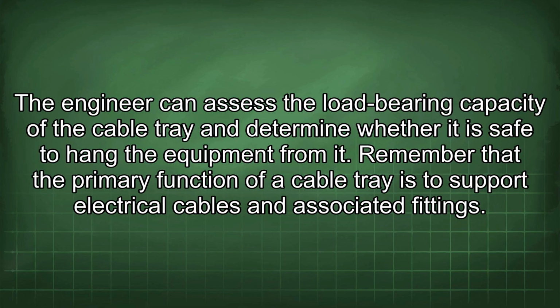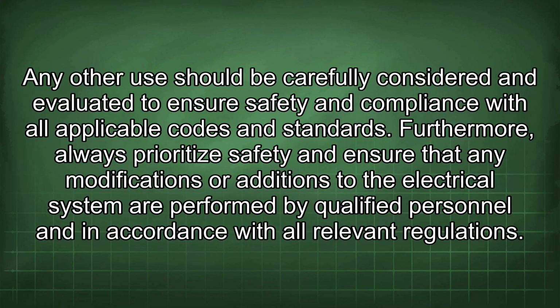The engineer can assess the load-bearing capacity of the cable tray and determine whether it is safe to hang the equipment from it. Remember that the primary function of a cable tray is to support electrical cables and associated fittings. Any other use should be carefully considered and evaluated to ensure safety and compliance with all applicable codes and standards. Furthermore, always prioritize safety and ensure that any modifications or additions to the electrical system are performed by qualified personnel and in accordance with all relevant regulations.